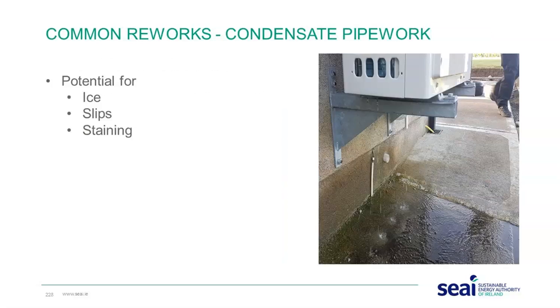Another thing is the condensate pipework. You can see from this image on the right, sometimes when you're doing an installation, things mightn't be as apparent as when, maybe a month and a half later, we do our inspection, and there can be more of a nuisance factor that didn't seem as big a deal at the time of installation. You can see clearly here from this image on the right, condensate has just fallen onto the footpath.